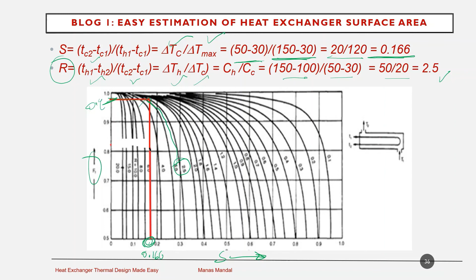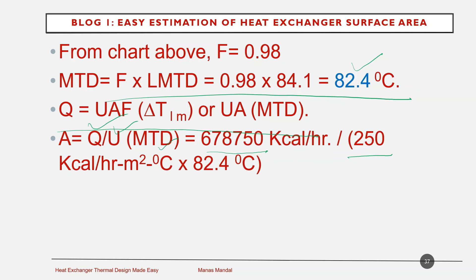Now we all know Q equals U A MTD. So Q is known to us, 678,750, divided by U given to us as 250, and we have already calculated MTD as 82.4, which is giving us 32.9 meter square of surface area required for this exchanger.